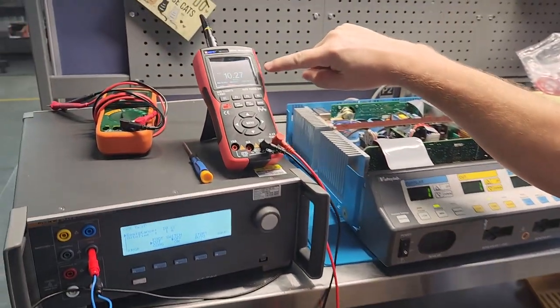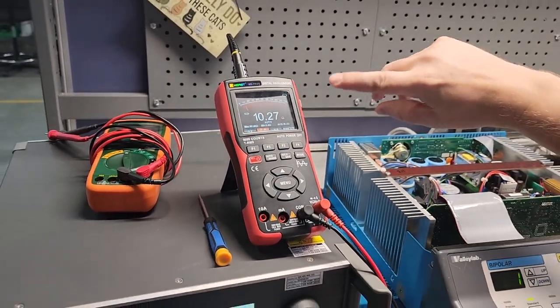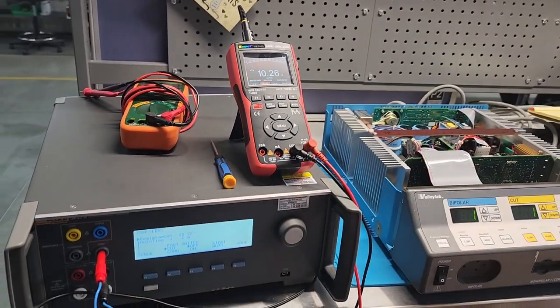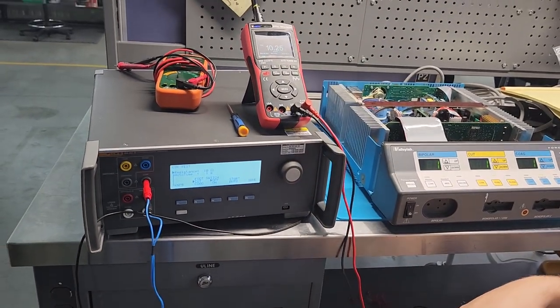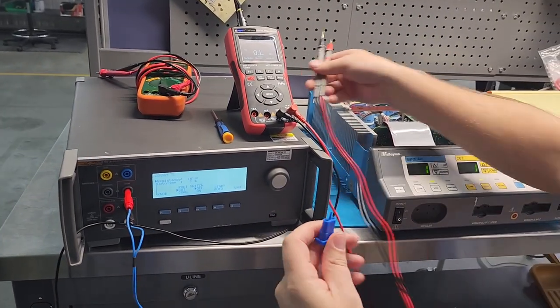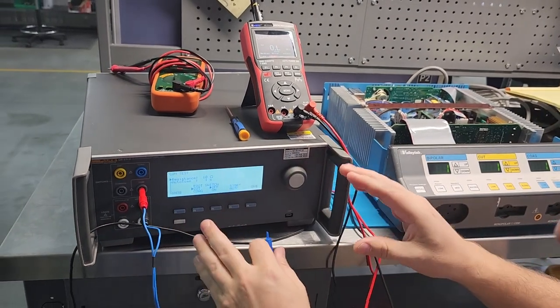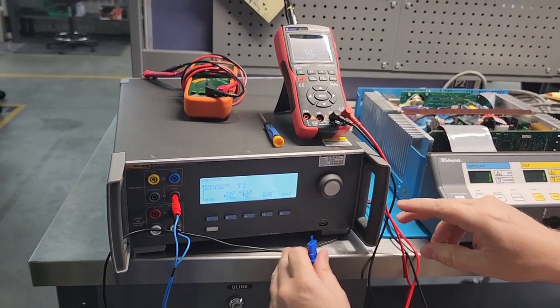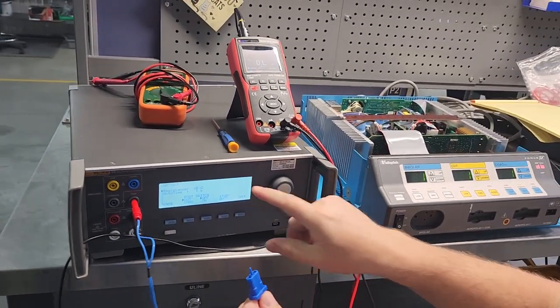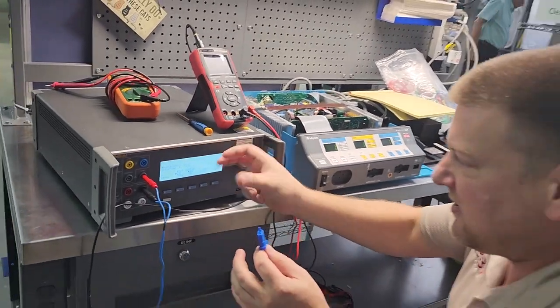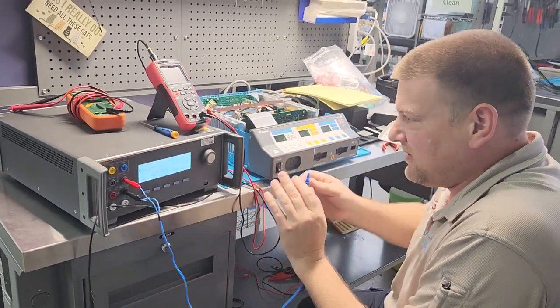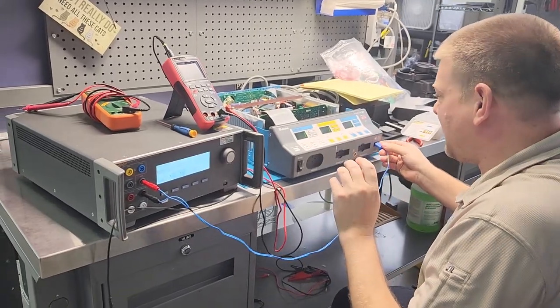you can stick the multimeter leads in. I just give them a little bit of squeeze pressure. And you can see right here, my multimeter, since it's not a Fluke multimeter, it's going to stabilize very slowly but that's okay. And I better hurry up and get this video done because you can see my batteries run low. So this guy is actually so easy and it's so nice to run through your resistance. You don't have to activate like normally you'd set the resistance and then activate. You don't have to do that with the QA ES3. You just set it and forget it.